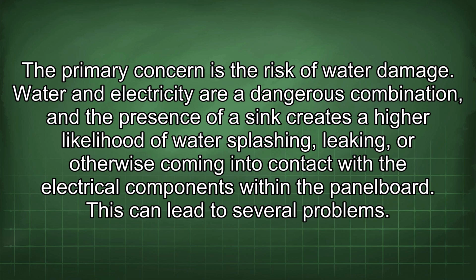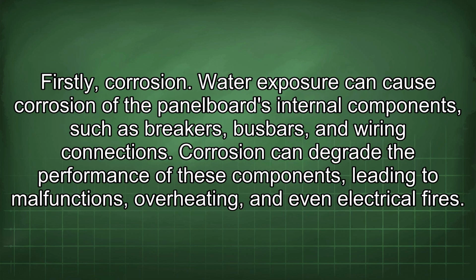Water and electricity are a dangerous combination, and the presence of a sink creates a higher likelihood of water splashing, leaking, or otherwise coming into contact with the electrical components within the panel board. This can lead to several problems. Firstly, corrosion. Water exposure can cause corrosion of the panel board's internal components, such as breakers, busbars, and wiring connections. Corrosion can degrade the performance of these components, leading to malfunctions, overheating, and even electrical fires.